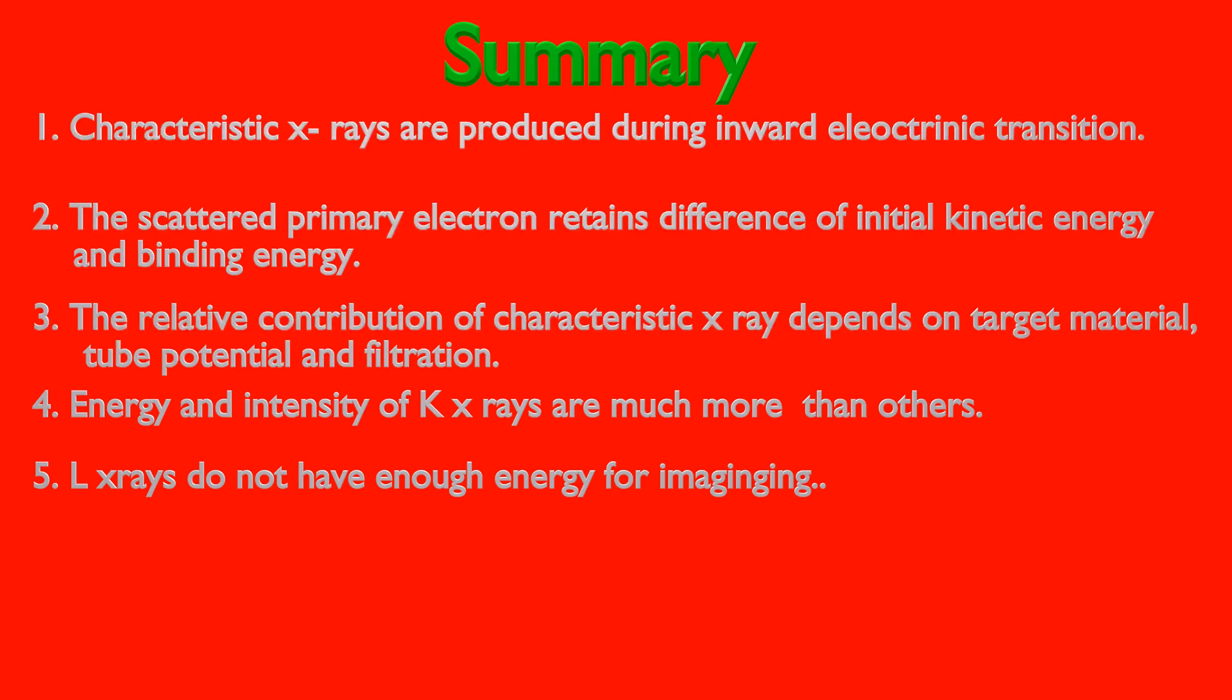Consequently, they are useless in diagnostic imaging. In fact, soft X-rays like L X-rays are totally absorbed by a typical filtration of 2.5 mm aluminium.